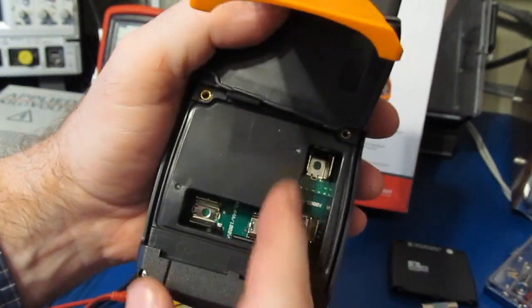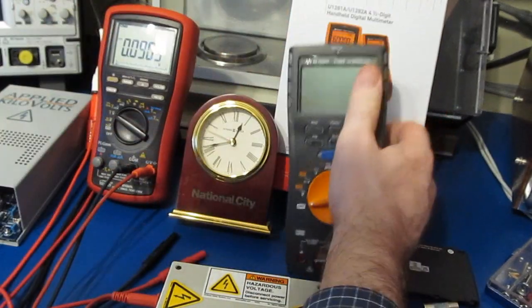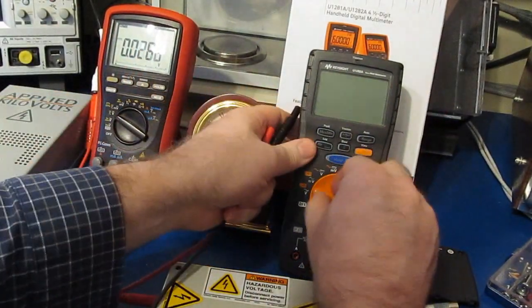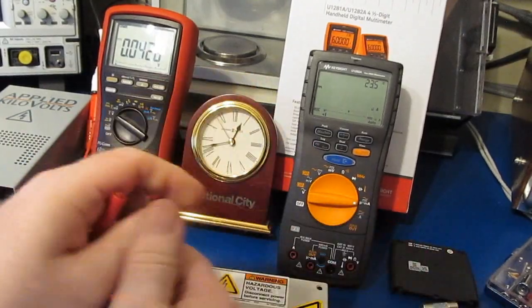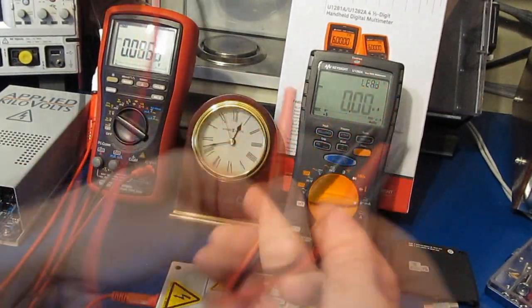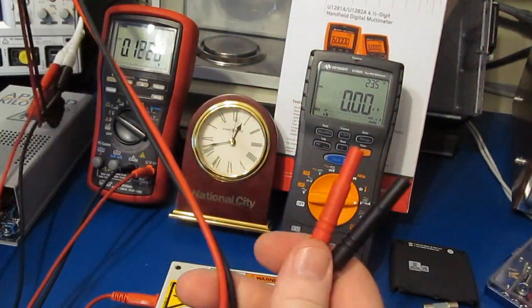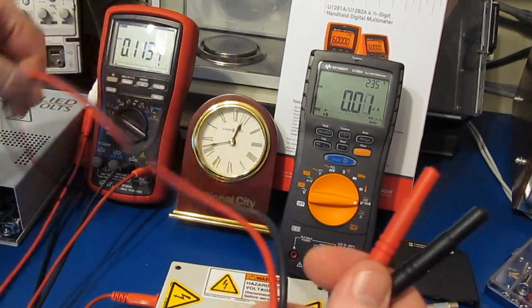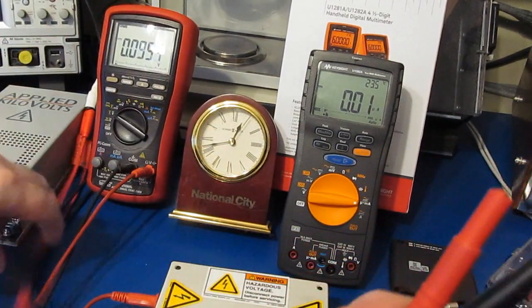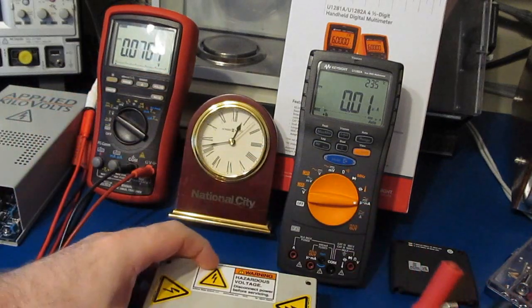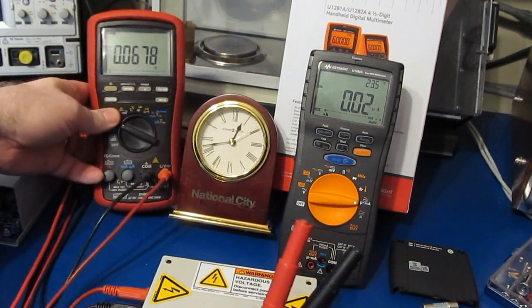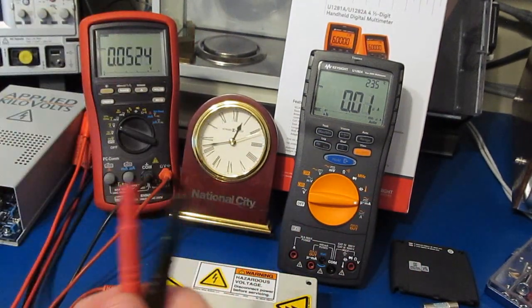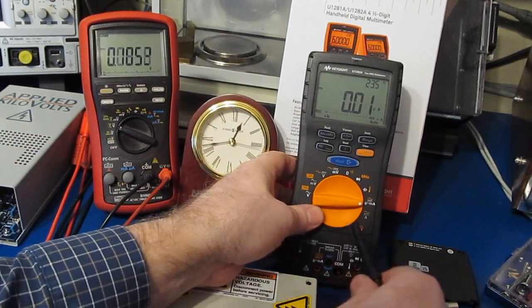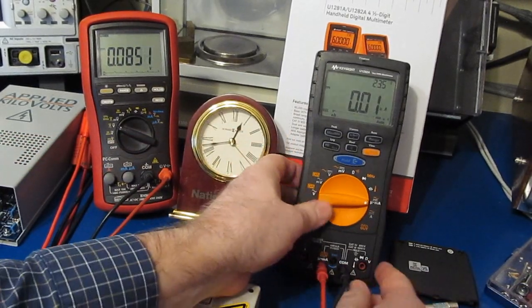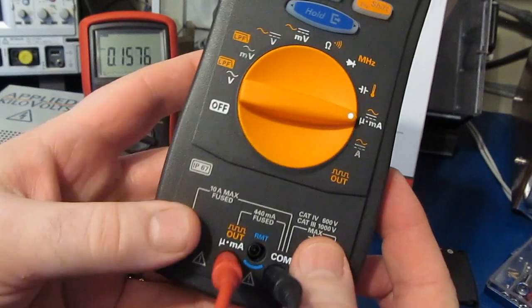You can see I've gone ahead and removed the two fuses again. We'll just leave that cover off, and again we'll place the meter into its microamp mode. These two leads here go back up to our power supply. The second set of leads again go down to our 10x attenuator, which goes off to the BM869 here on the left. Again, we're going to be applying 2000 volts, or 2 times the maximum rating of the meter.